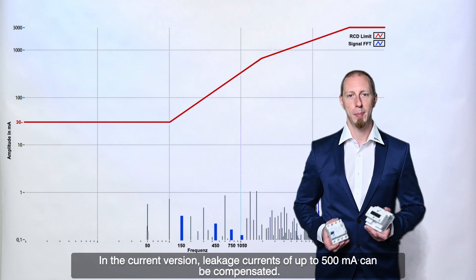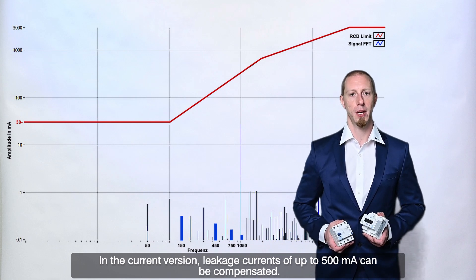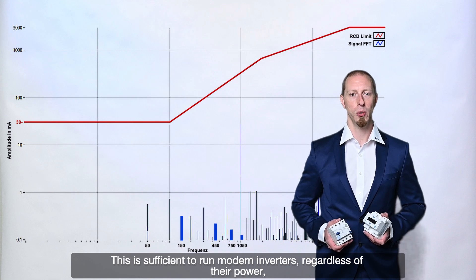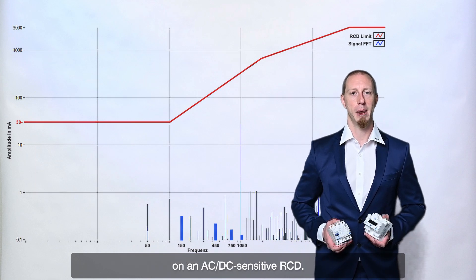In the current version, leakage currents of up to 500 mA can be compensated. This is sufficient to run modern inverters, regardless of their power, on an AC-DC sensitive RCD.